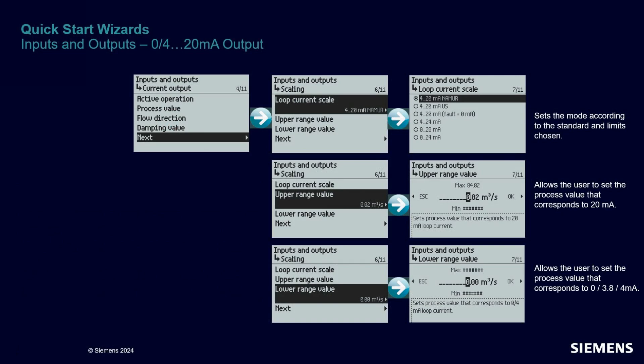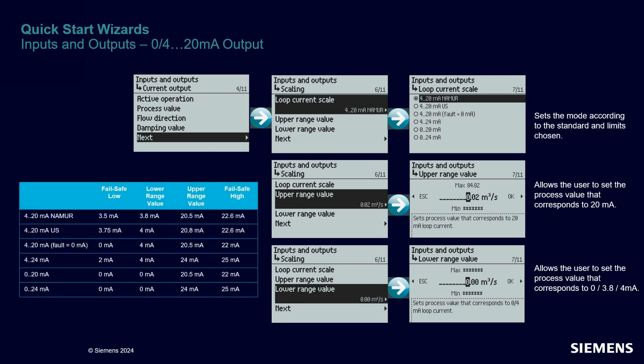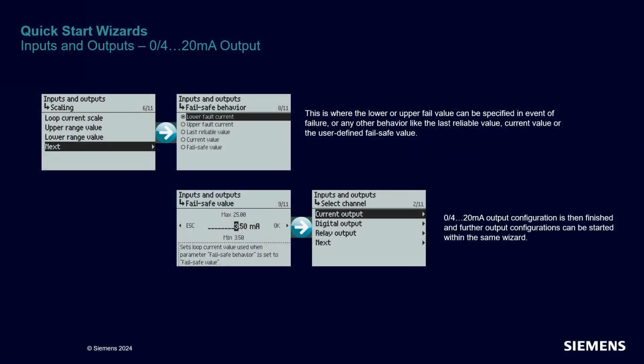Next, you must set the limits of your milliamp output. You can pick between multiple modes, which have different failsafe values and range values. It is up to you to select the ones that match your process controls. It is also at this stage that you configure the range values based on your process. The last configuration step is the failsafe behavior and its value. Now your milliamp output is configured and ready to go.